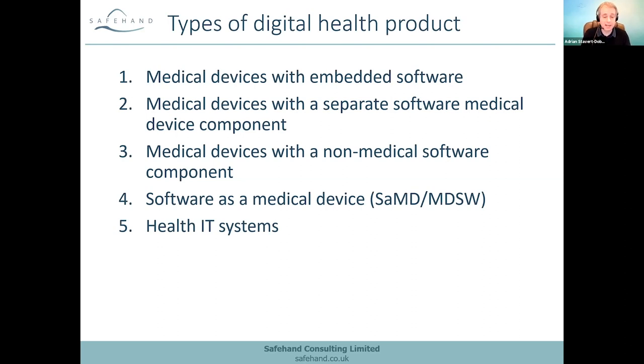The third category is similar: a medical device where the software component is, for some reason, a non-medical device because it doesn't meet the medical device criteria. A good example might be a vital signs monitor, where data is taken and stored on a remote database for future archive and retrieval, but without processing it in any way.